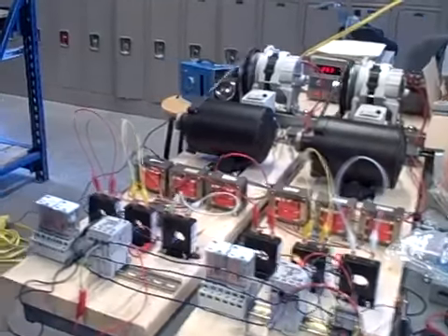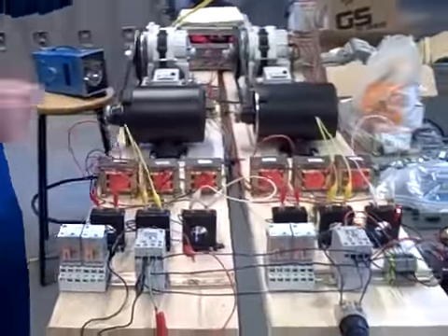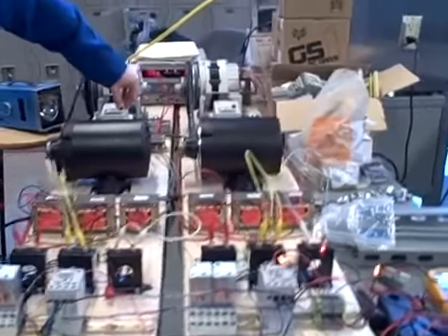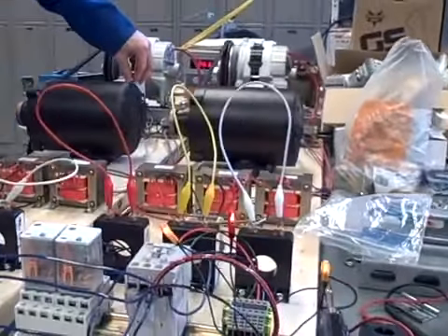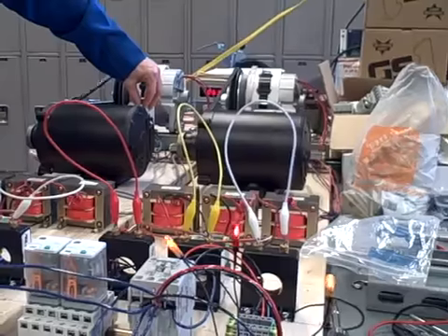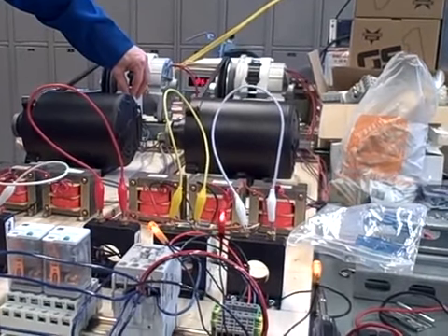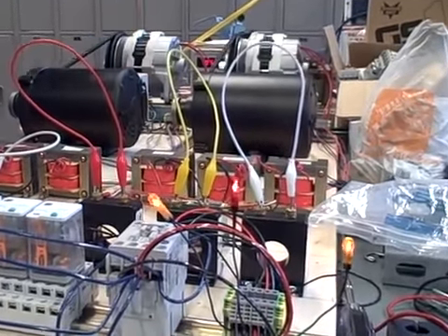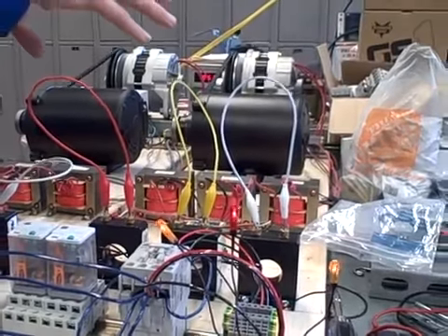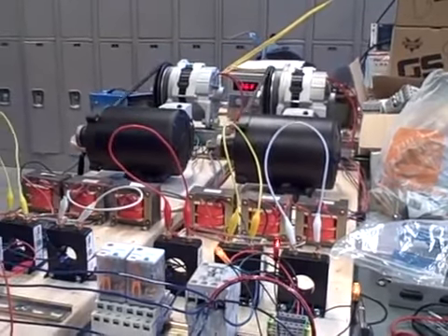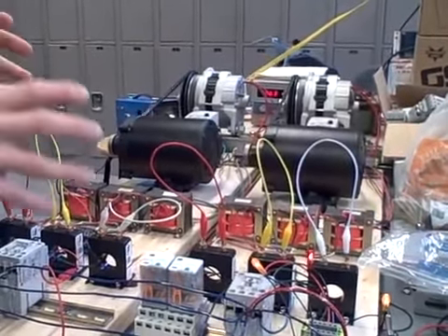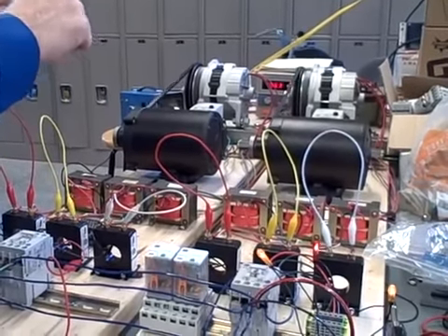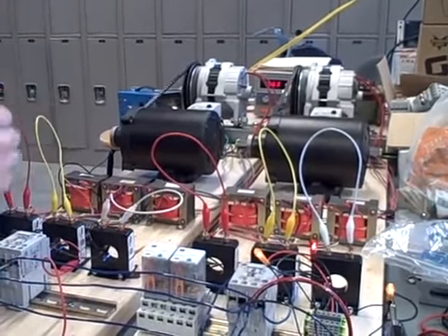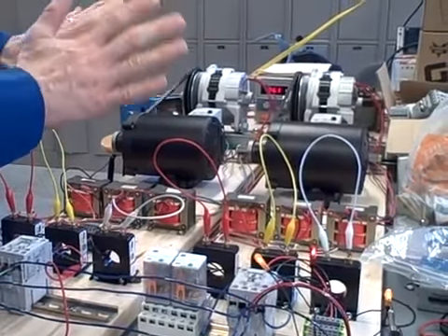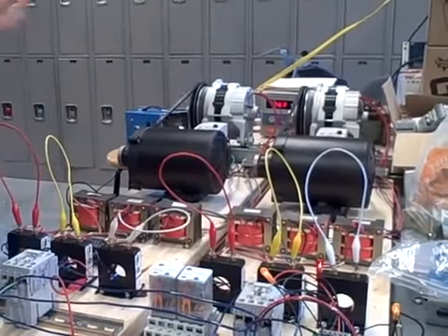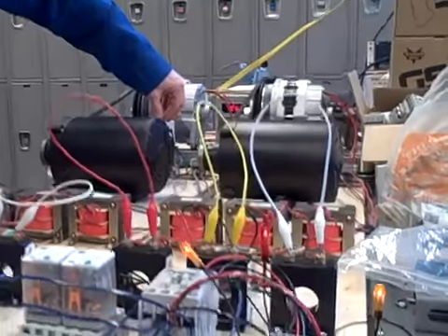So what I'm going to do is change the speed of this one generator over here, and you'll see the blinking rate change. So right now I'm going too slow. If I go slower yet, you see the lights blink faster. If I go slower yet, it blinks even faster. The slower this generator goes in comparison with the other one, the faster they roll in and out of phase with each other. So in order to make these suitable for synchronizing together, for closing that breaker and getting them in parallel, I need to get them in phase to the point where these lights are off and staying off. So watch me as I speed this generator up.